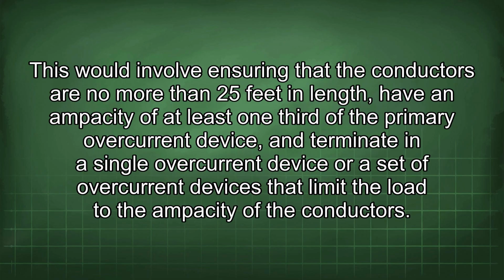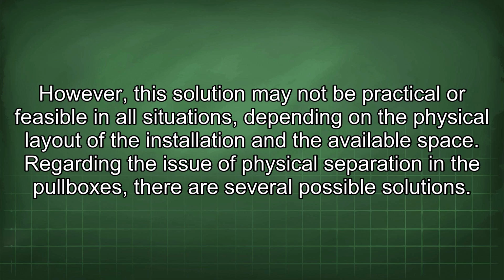This would involve ensuring that the conductors are no more than 25 feet in length, have an ampacity of at least one-third of the primary overcurrent device, and terminate in a single overcurrent device or a set of overcurrent devices that limit the load to the ampacity of the conductors. However, this solution may not be practical or feasible in all situations, depending on the physical layout of the installation and the available space. Regarding the issue of physical separation in the pullboxes, there are several possible solutions.